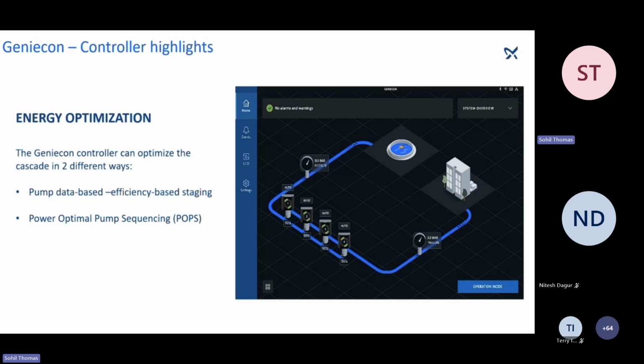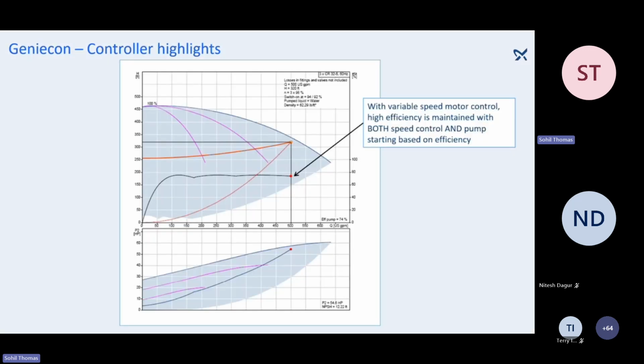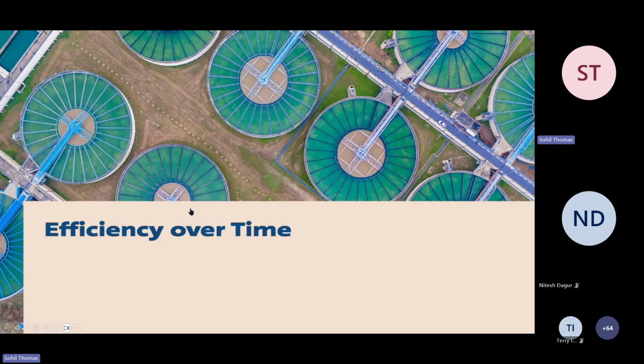So what that means is, let's suppose there is a requirement for 100 gallons per minute to be run. And if the system calculates that it is better to run 2 pumps at 60% speed than running 1 pump at 90% speed, it opts for that option to make sure less energy is consumed, and at the same time you're not compromising on the efficiency as well.